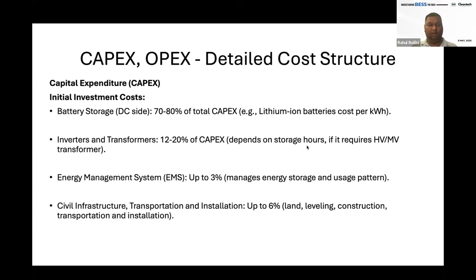Next thing is replacement and maintenance. One must understand that you need to do system balancing. On system balancing days, you cannot do 0.5C charge discharge — you'll have to do a very slow charge, very slow discharge. So maybe on those days you may have some losses if you're not able to meet your commitments. But yes, that's a mandate, especially for projects after 2 years.